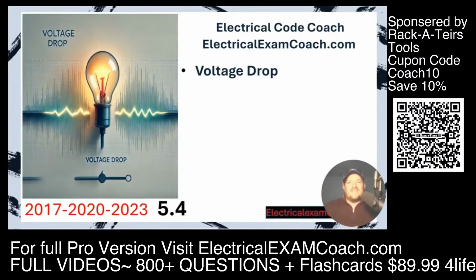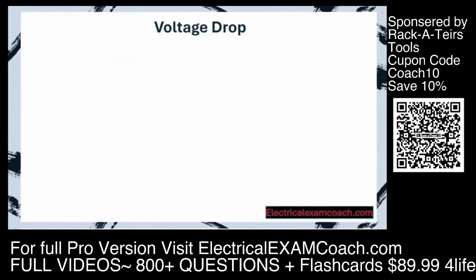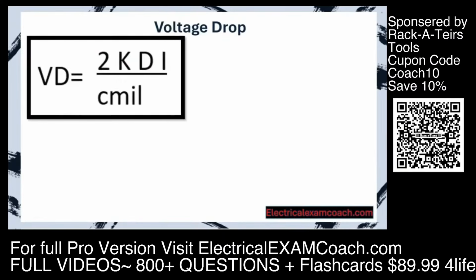Let's get to it. If you were to do an internet search for a voltage drop formula, you would likely find this one right here. Voltage drop equals 2 kDi over C mil. And that is an excellent formula. And it's actually the one that I use. But I've rearranged it so it's easier to remember.